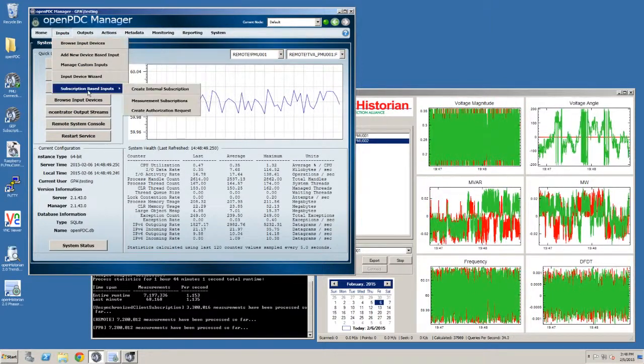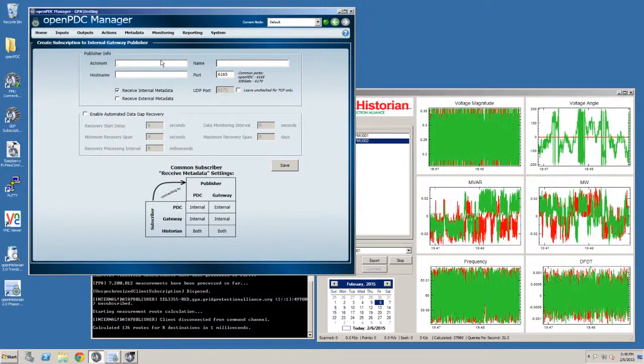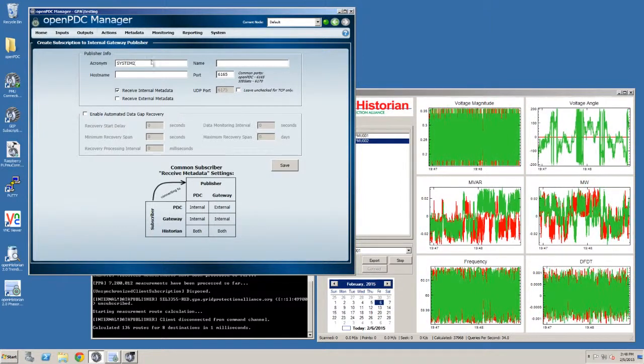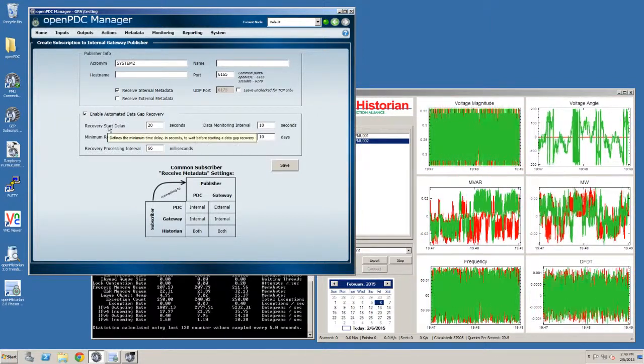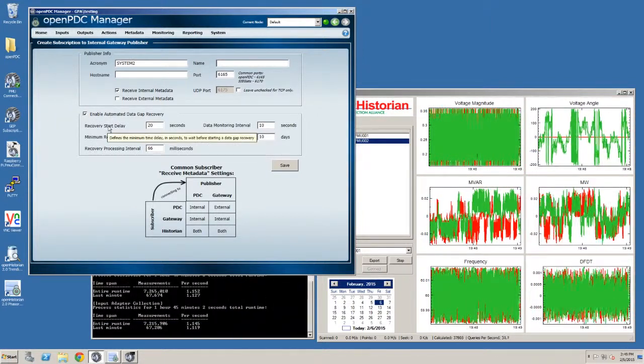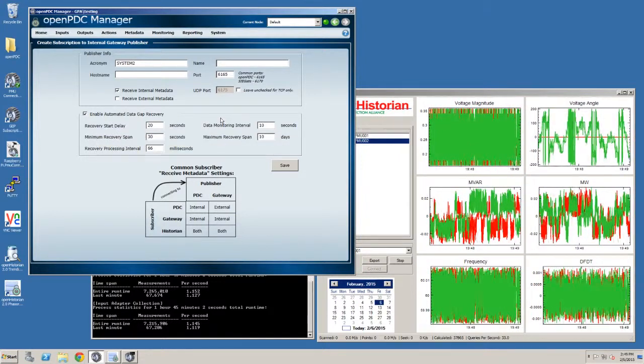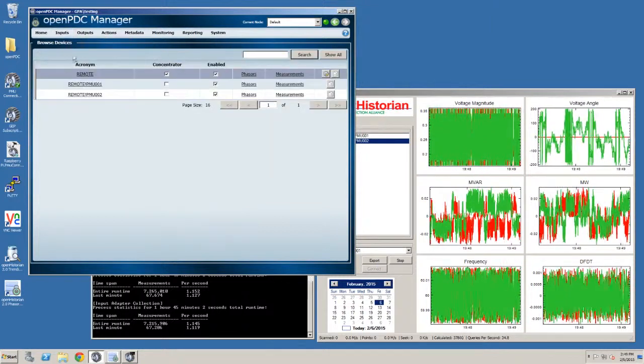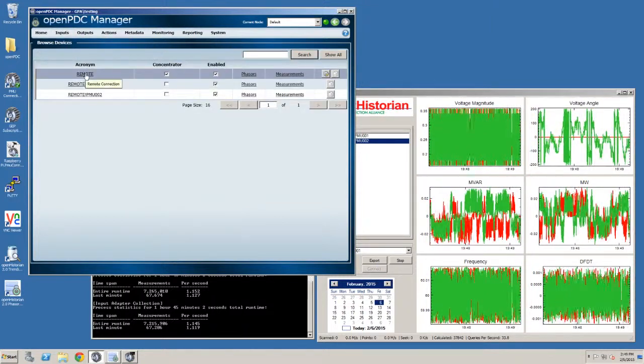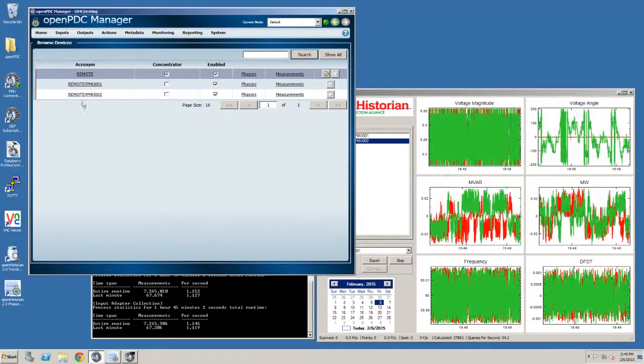You'd fill in the properties. And then you would check the box for automated data gap recovery. And you have some options you can fill out. But they're set to some reasonable values. And generally, if you just wanted to automatically get data, you just hit save. So this one's already been set up. So we have a connection to the remote system. And that is a gateway exchange protocol kind of session. And it's connected to two PMUs.